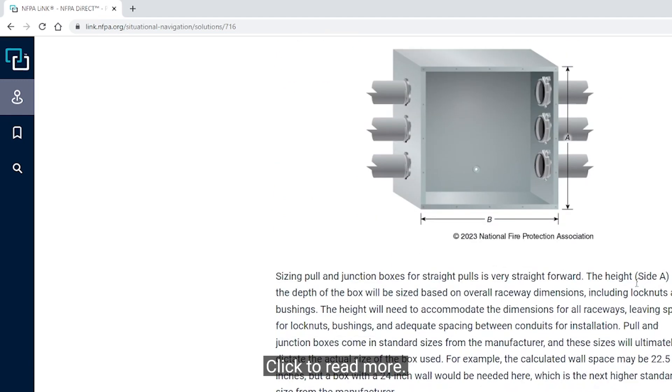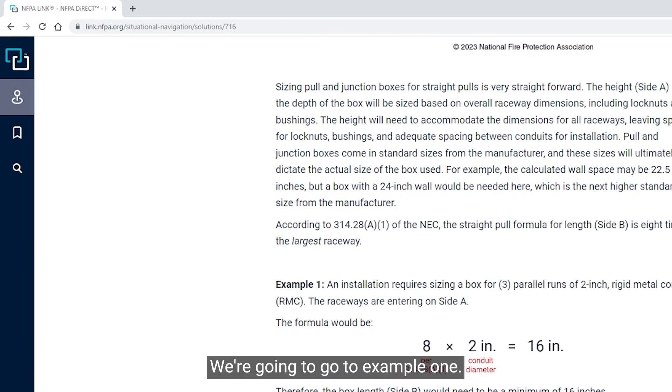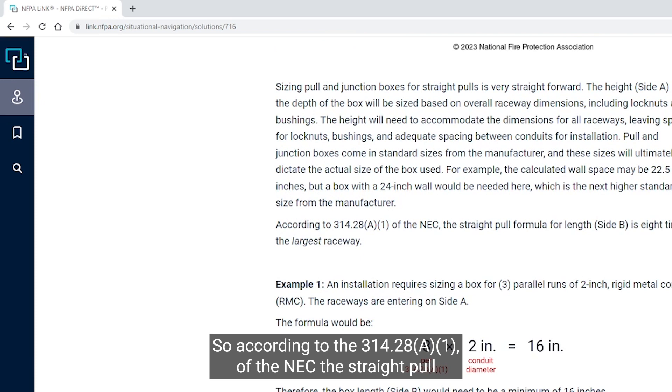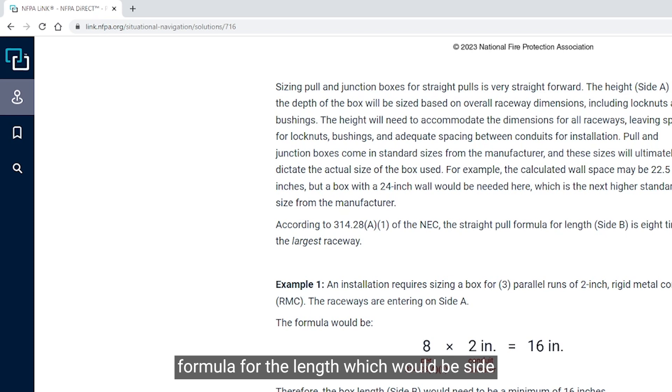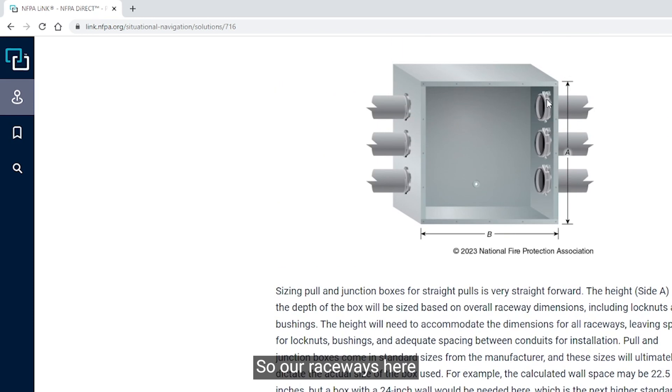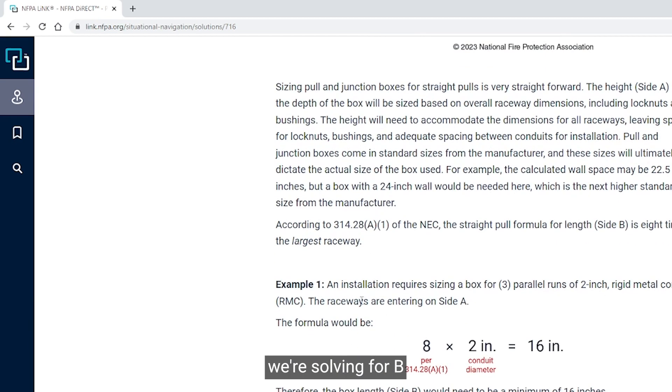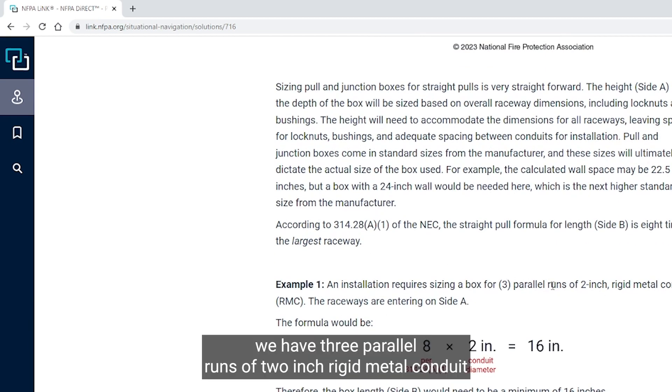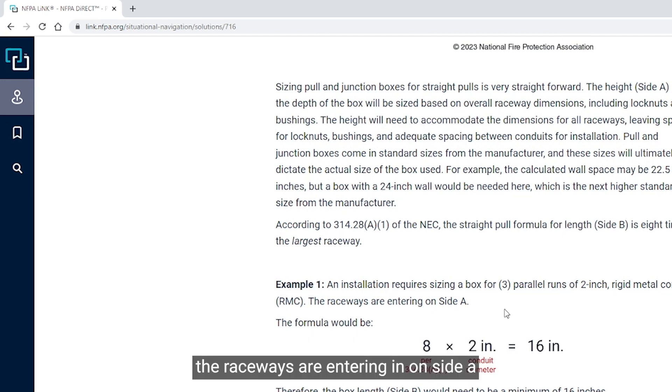For example, the calculated wall space may be 22.5 inches, but because it's not a standard size from the manufacturer, the box that's chosen is a 24-inch wall space. So we're going to go to Straight Pulls under .1 and click Read More. We're going to go to Example 1. According to 314.28(A)(1) of the NEC, the straight pull formula for length, which would be side B, is eight times the largest raceway.